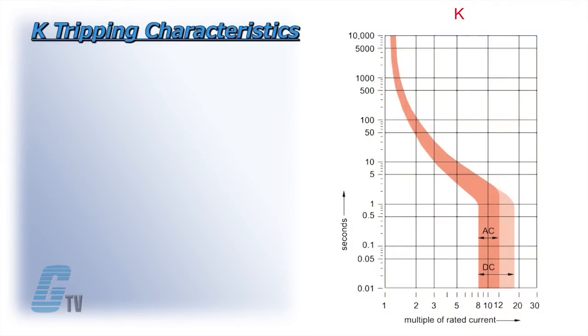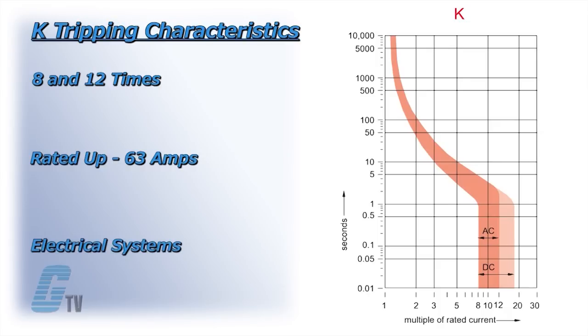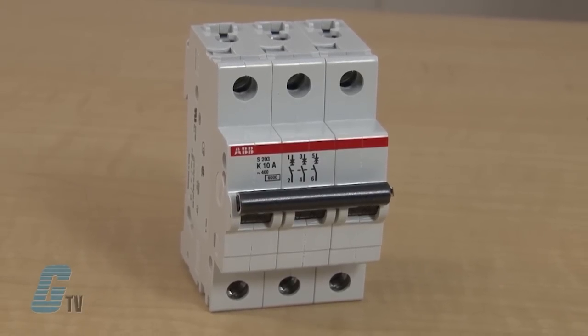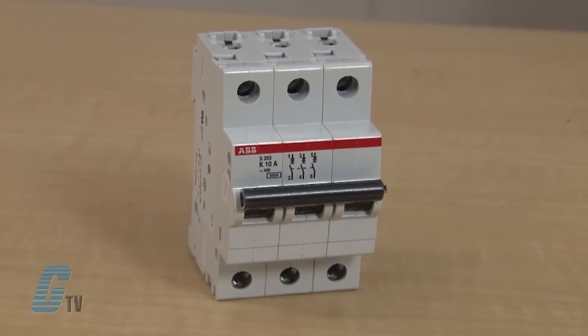The K tripping characteristic considers high magnetic start-up currents for motors, transformers, and other equipment. Instantaneous tripping occurs between 8 and 12 times rated current in 50 or 60 Hz systems. The K breakers are available up through 63 amps. The K curve offers the best protection for the broadest range of electrical systems. The higher magnetic trip settings maximize protection while allowing for higher in-rush currents during system start-up.